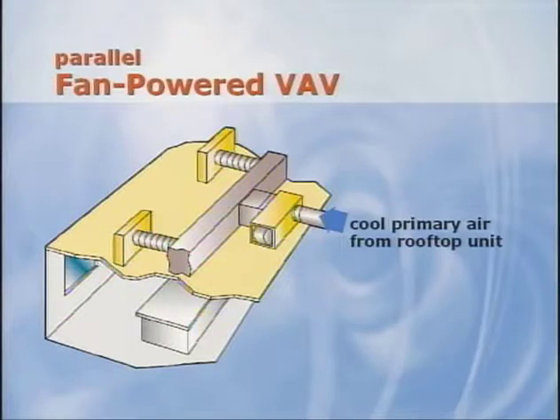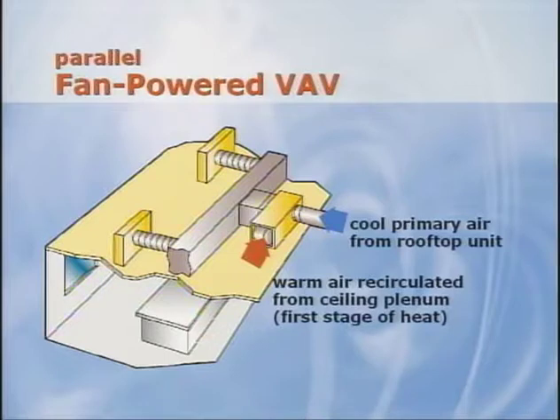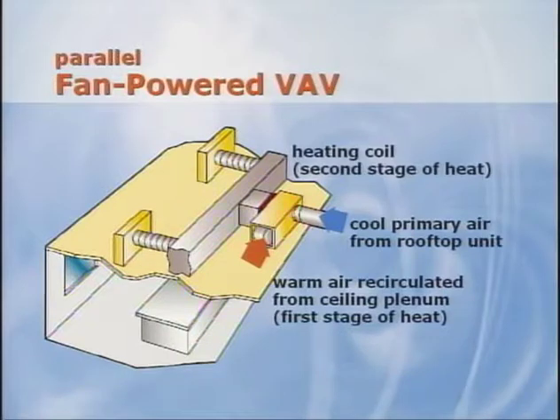Heat generated by light fixtures warms the air in the ceiling plenum. Fan-powered VAV boxes use this warm air from the plenum as a form of heat recovery. In a parallel fan-powered VAV box, primary airflow is reduced as the cooling load decreases. When the box reaches its minimum airflow setting, the small fan activates to draw warm air from the ceiling plenum and mix it with cool primary air. If more heat is required, the heating coil can be activated. Parallel fan-powered VAV boxes can save energy because they use warm air from the ceiling as the first stage of heating. This delays the need to use new energy by activating the heating coil.